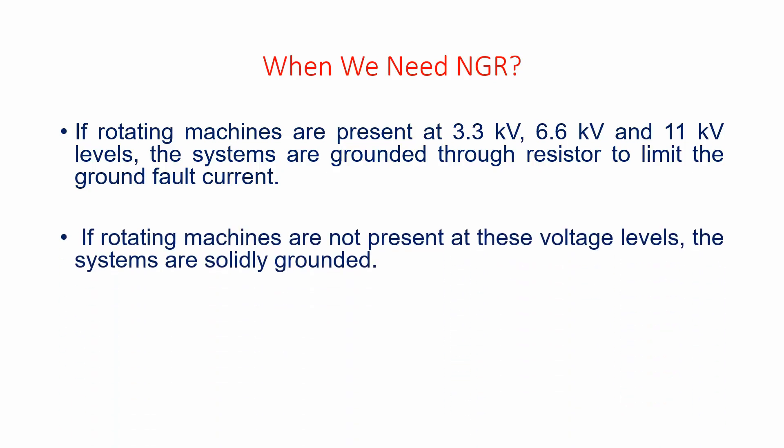If rotating machines are not present at this voltage level, it is not mandatory to go for neutral grounding resistor. Solidly grounded systems are more than enough.